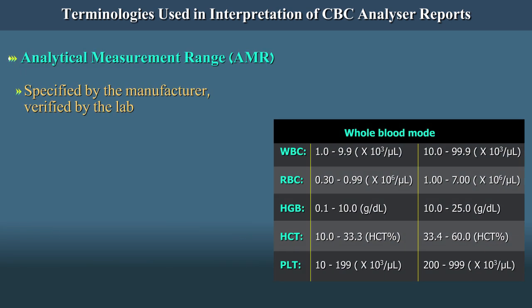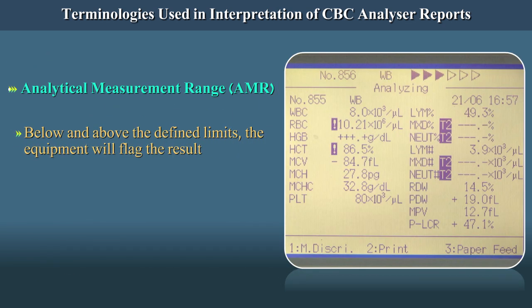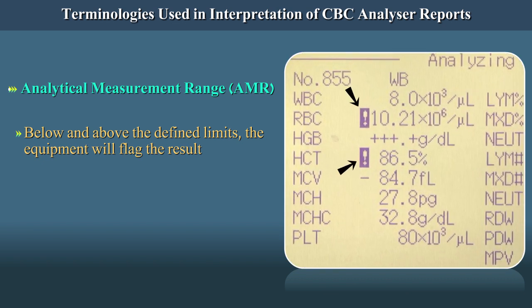This range is also called the linearity and is specified by the manufacturer but needs to be verified by the lab. This range is fed in the machine by the manufacturer. Every equipment has an analytical measurement range which is the linearity limit for the analyte with possible errors at varying levels. The upper and the lower limits will be specific. Below and above the defined limits, the equipment will flag the result.